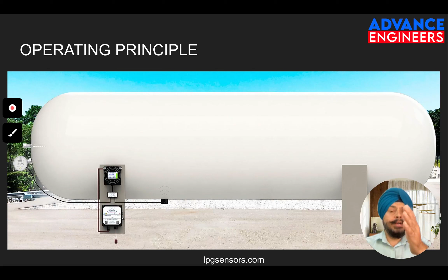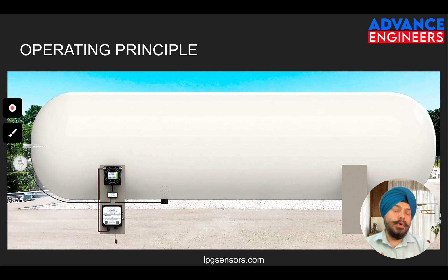So what it does is it sends a wave from the bottom, via the walls of the vessel, and it crosses the vessel's wall, then goes directly to the liquid level, the highest interface level. Whenever there is an interface level, when the waves move from denser to lighter medium or lighter to denser, there is a reflection going on, and that reflection is measured by this sensor. So these sensors calculate how much these waves have traveled in the LPG, and from there it has come back. It calculates and tells you what the distance to the LPG is. This is the direct measurement of LPG from here.